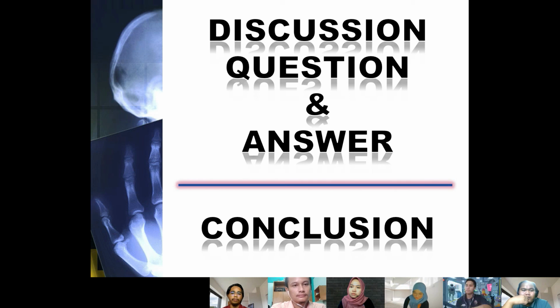The device is strictly banned from reprocessing, like cleaning, disinfecting, or sterilizing, and later being used on another patient. The reason is to avoid infection of other patients, which may cause more severe disease or even worse, death. So that's why the single-use designation device must be disposed of properly. I hope that answers your question. All right, Amma, thank you.